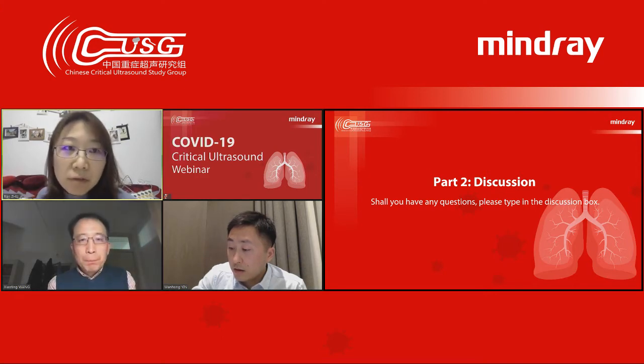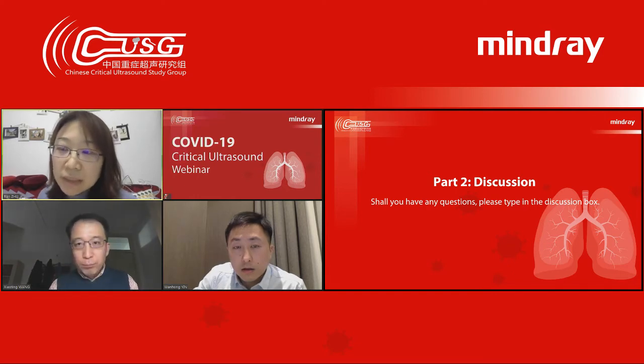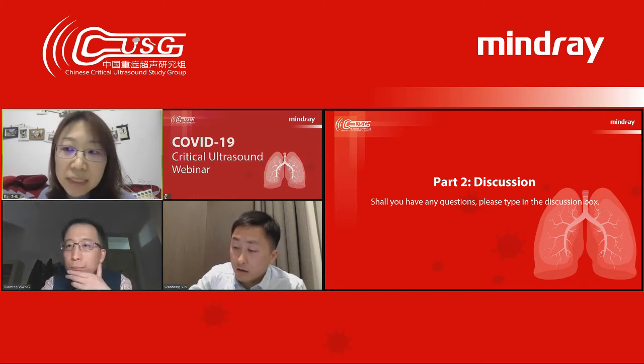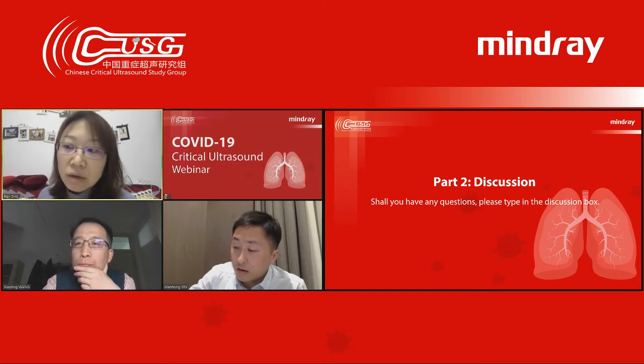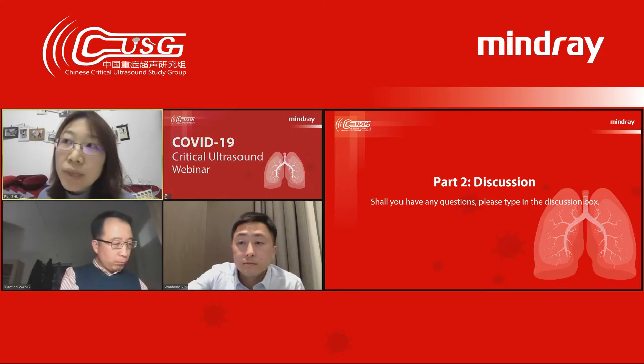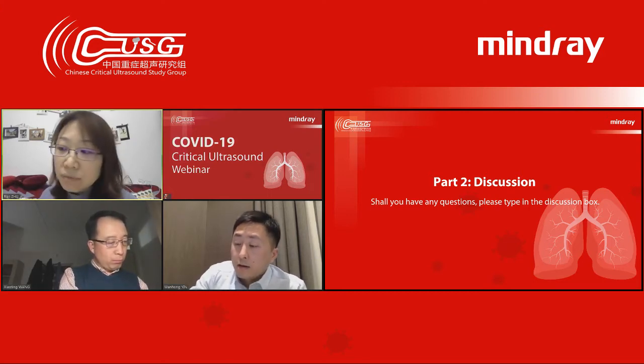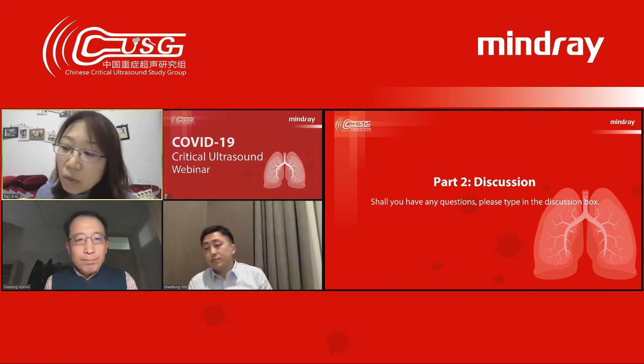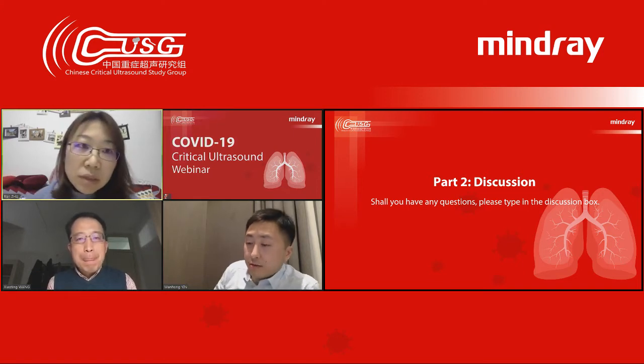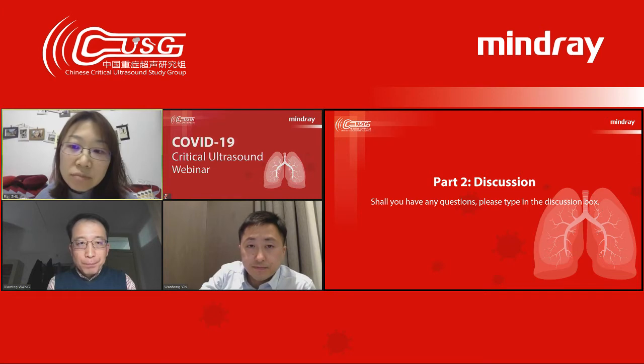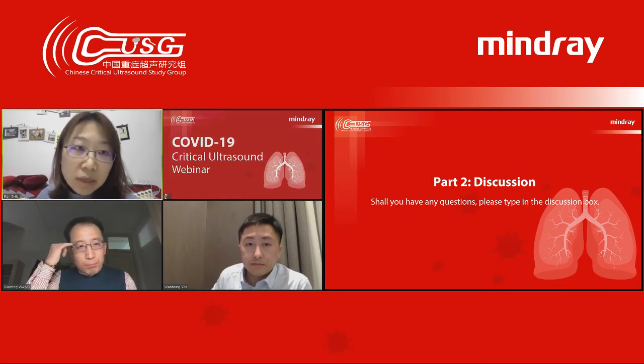For the probe and the line, we must disinfect them thoroughly before and after the examination, just as we do when we use the ultrasound machine to examine our regular patients, not COVID-19 patients. Usually for that disinfection, we use wet towels containing ammonium salt or hydrogen peroxide, so that it will not be harmful to our probe, I mean, it will not decrease the efficiency of the probe over a long time. That's what we use for our probe and line. And if we want to use the ultrasound machine to guide some sterile procedure, like ultrasound guided CVC injection or ultrasound guided PICC injection.